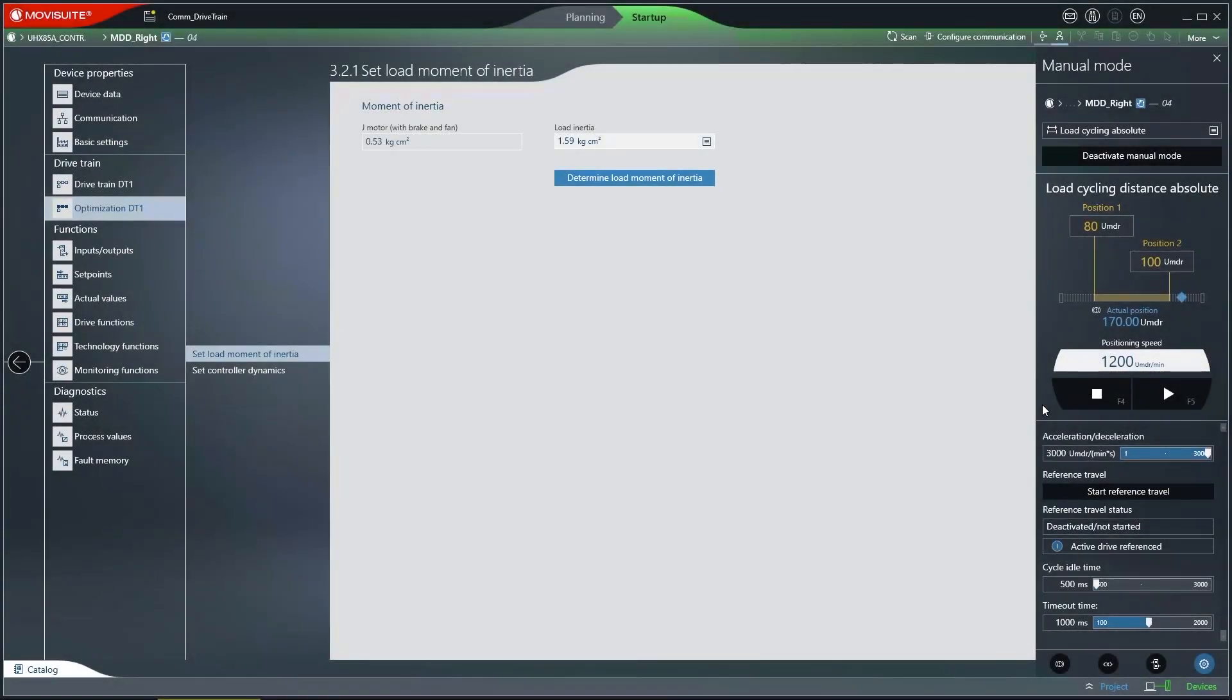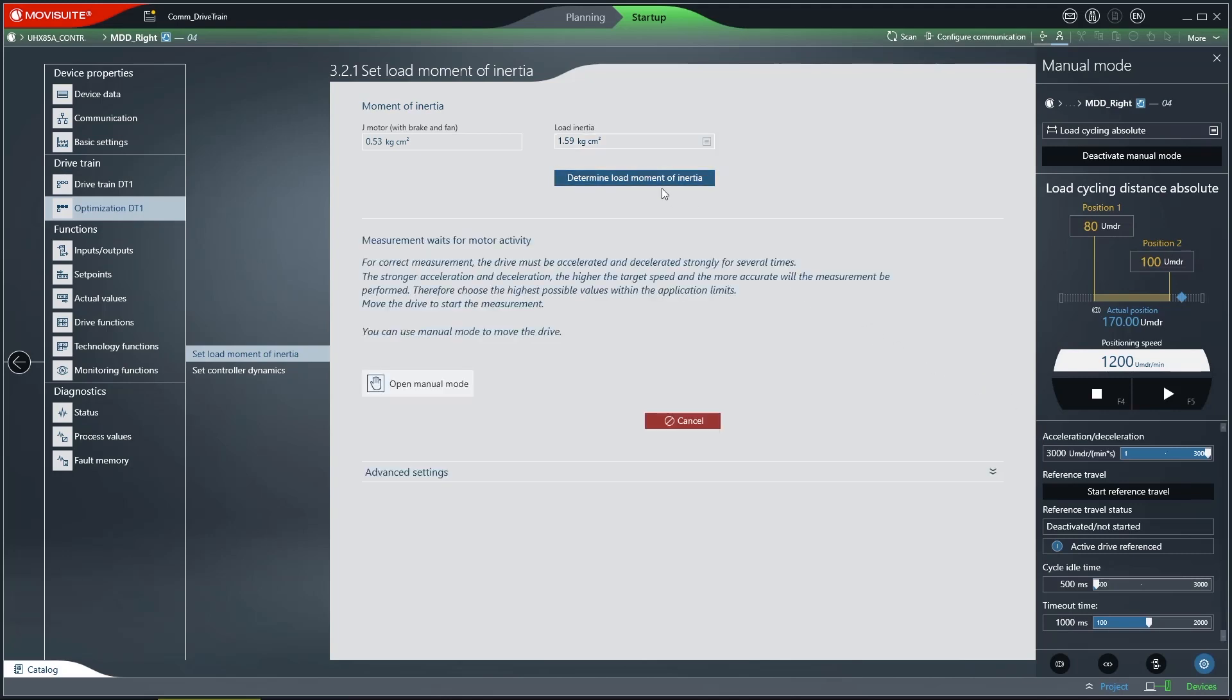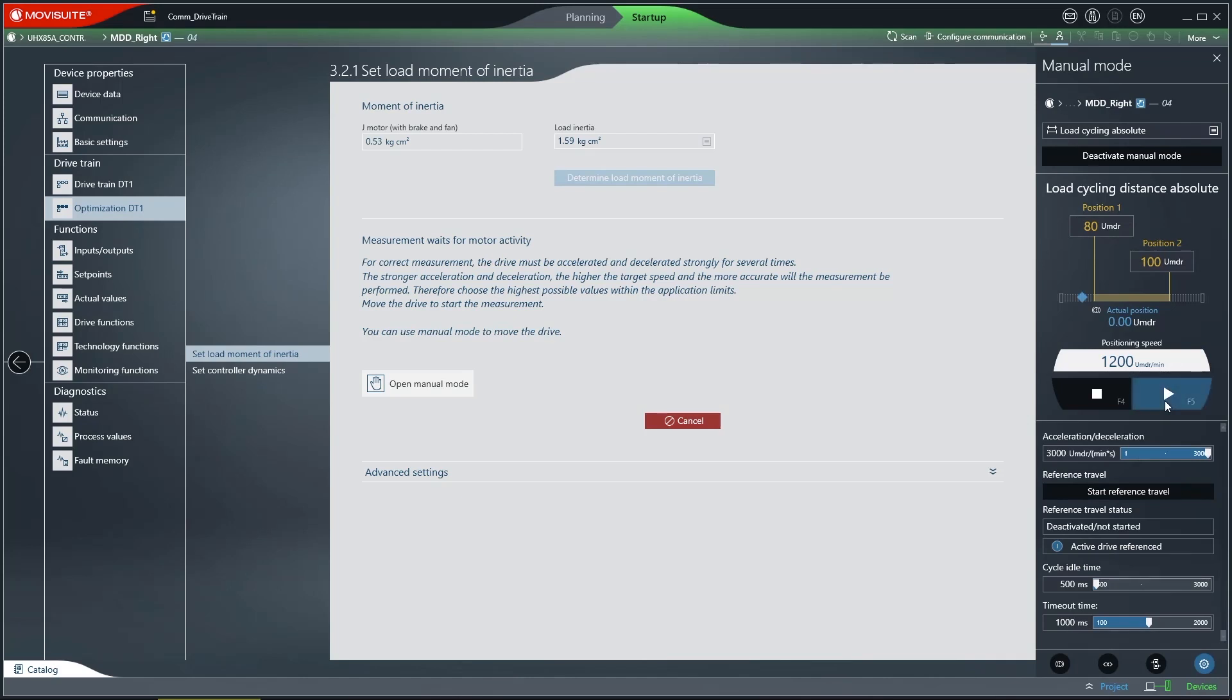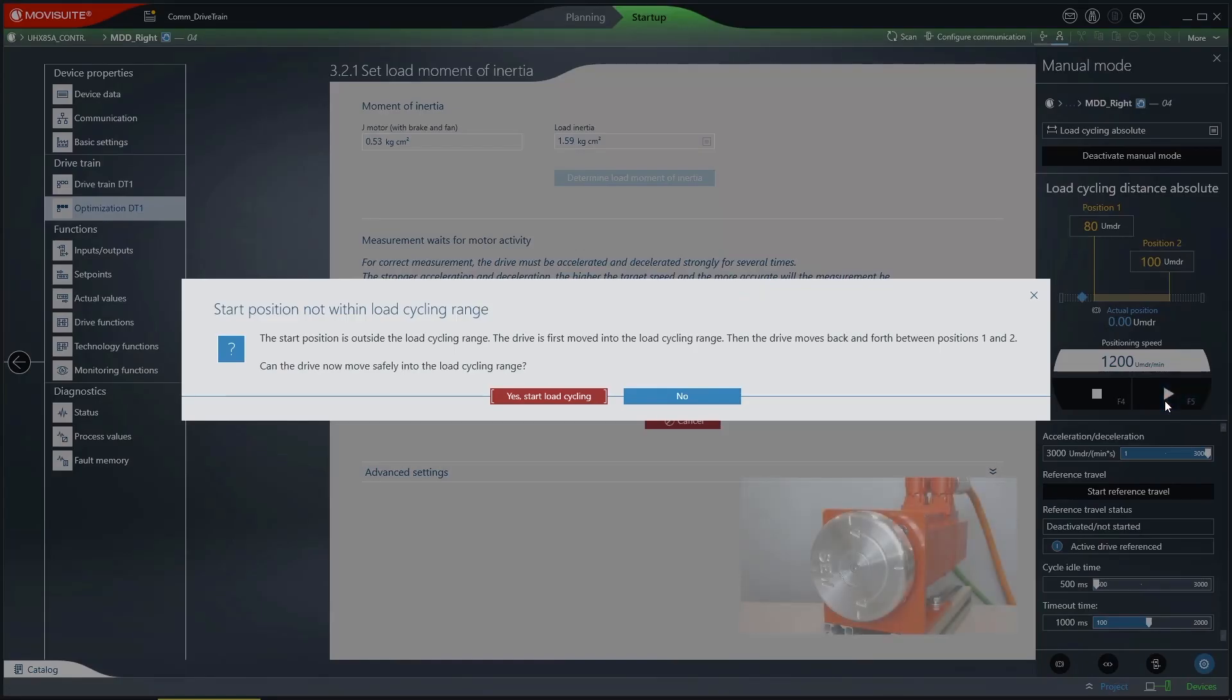The load moment of inertia that is present on the motor shaft is often unknown. MOVISUITE provides you with the ability to determine this. Since recurring strong acceleration and strong deceleration are required to do so, the load cycling or cycle mode are extremely well suited here.